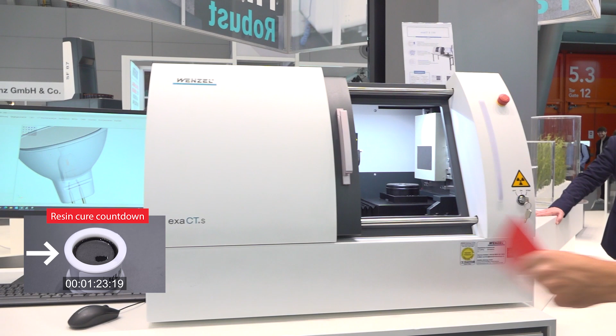Now, this is 130 kilovolt, which is absolutely huge for a machine of this size. Normally, you won't be able to fit a machine of this size on a table like this. And the size that you can scan, let me grab this here. The size that you can scan is 83 millimeters by 46 millimeters high.